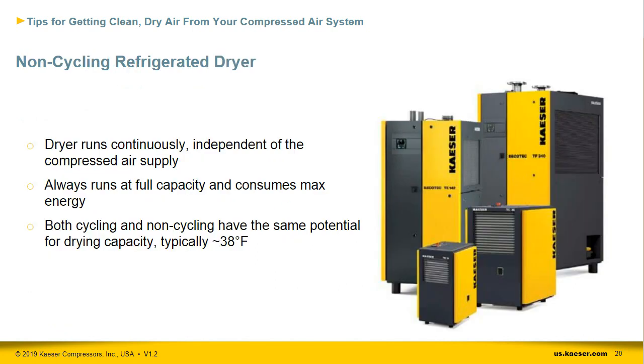Non-cycling dryers are some of the more basic refrigerated dryers. They run continuously regardless of the amount of compressed air running through them. This doesn't affect the dew point of the air leaving the dryer, but does cause the dryer to consume a maximum amount of energy on a regular basis. Essentially, the dryer does its job, but doesn't do anything to mitigate any energy consumption.